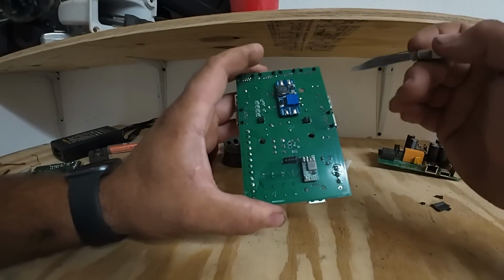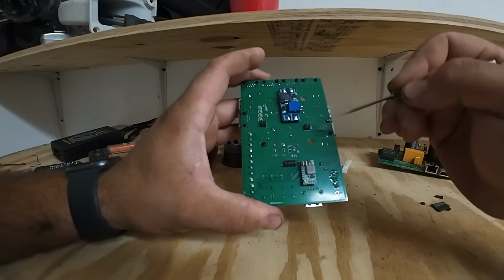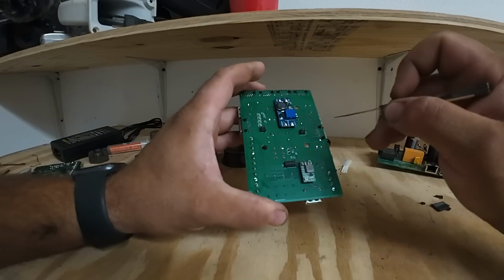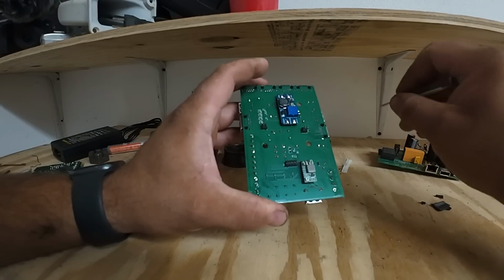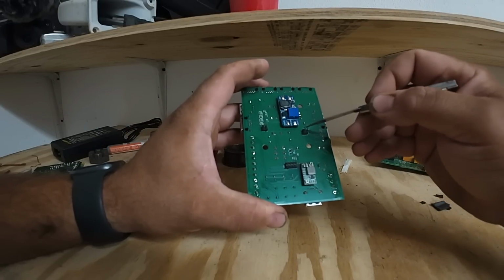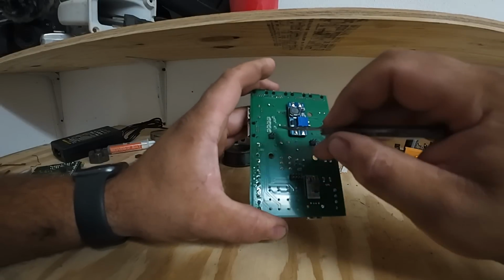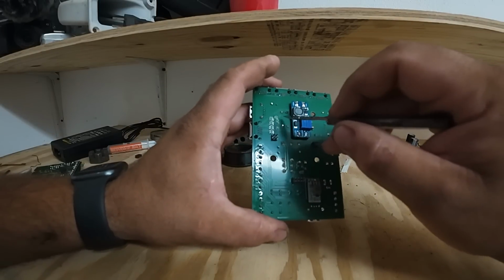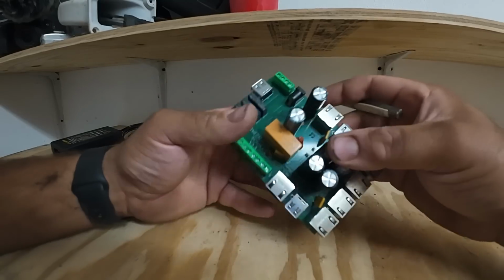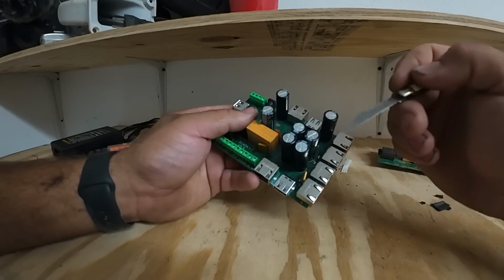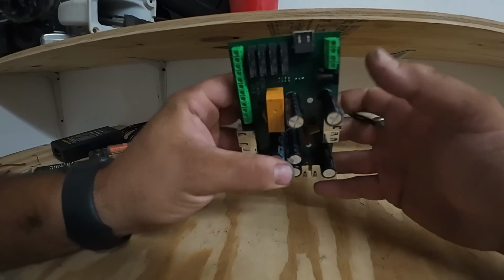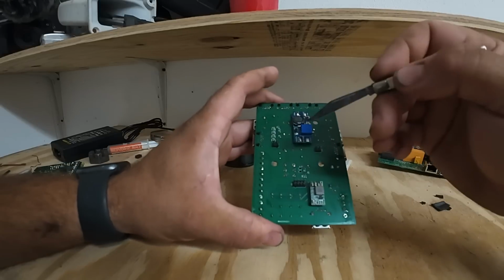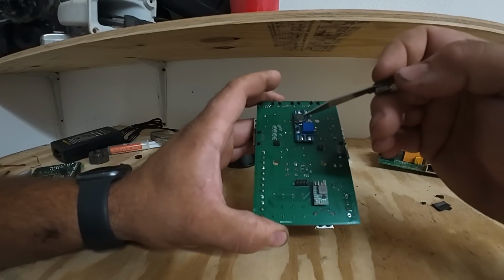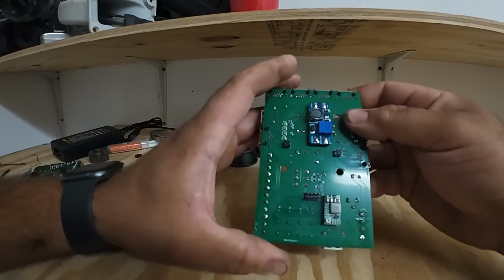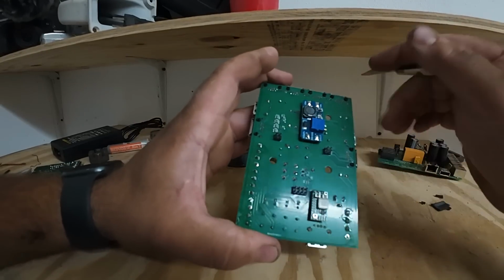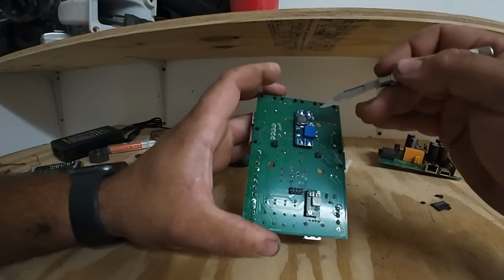The 0 to 5 volt stuff is similar. We're sending 2 ground wires and 2 5-volt positives out. The sensors come back and they connect directly to these. Also, these 4 to 20 milliamp sensors use one of these 4 capacitors, and these capacitors are simply filtering capacitors. The 4 to 20 milliamps seem to have some relatively high-speed noise in it that the capacitors more than take care of.